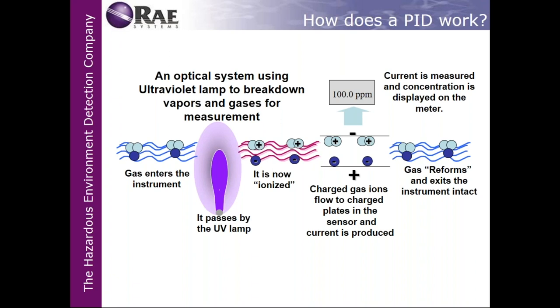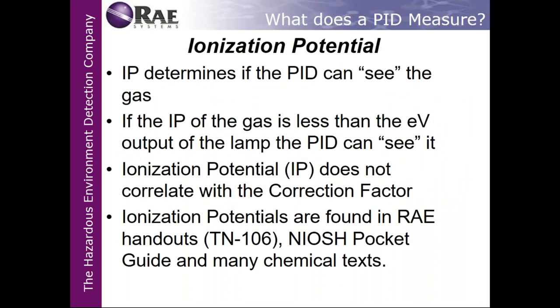So remember, it's a non-destructive way of measuring gas. When you're using an LEL sensor, you're actually burning a sample, and that burning is being measured. In a PID, the electronic charge or voltage gets measured, and then the VOC comes back as normal, like I said in my gas analogy. Pretty interesting graphics there, huh?